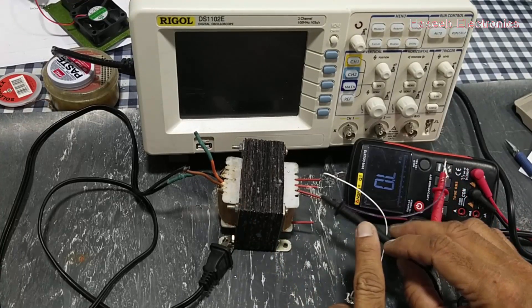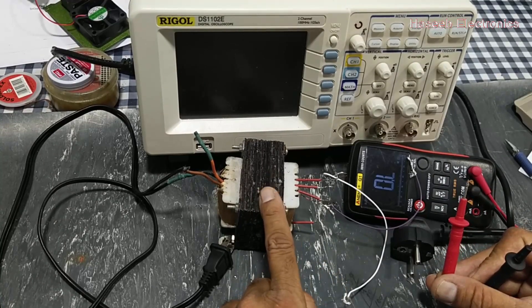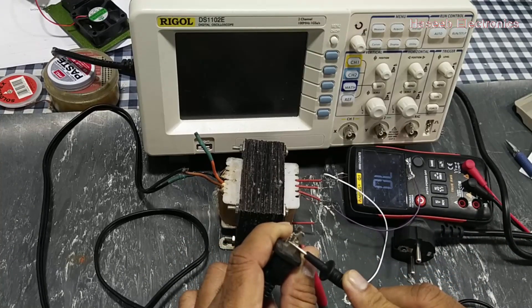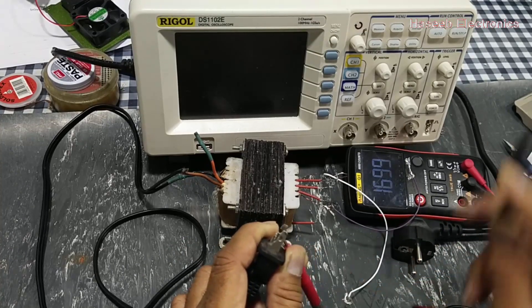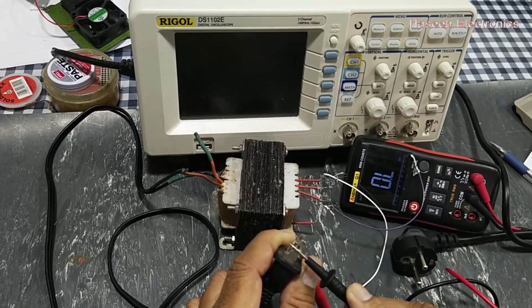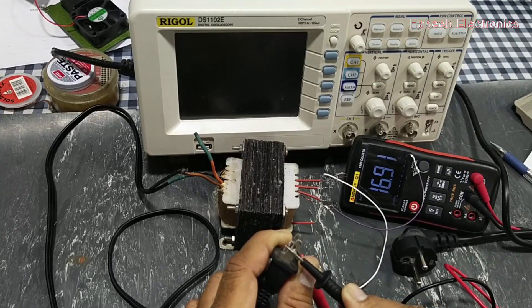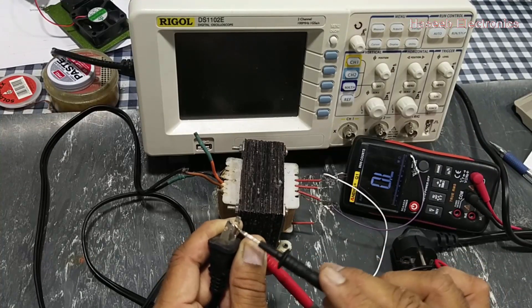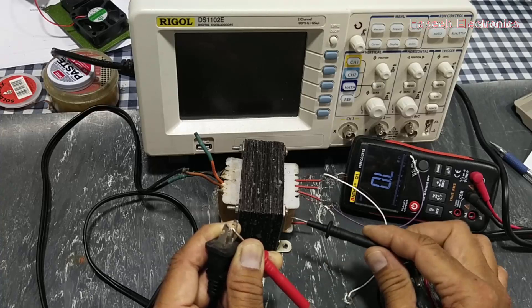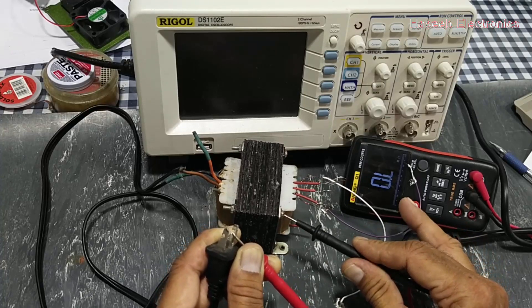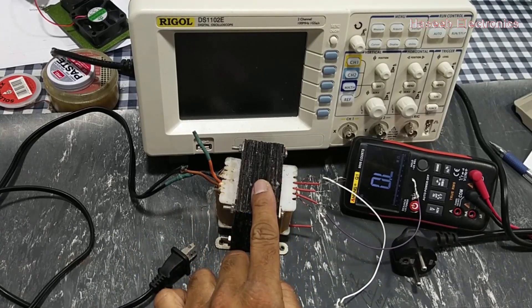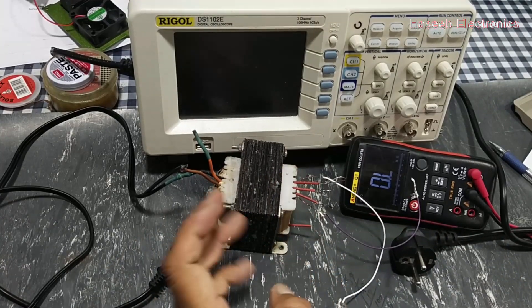Now the primary side. Primary side 16.9 ohms. Connect one lead to the primary input terminal and to the chassis, so it is open. It's good. So this is the isolation testing of any transformer. It must be insulated.